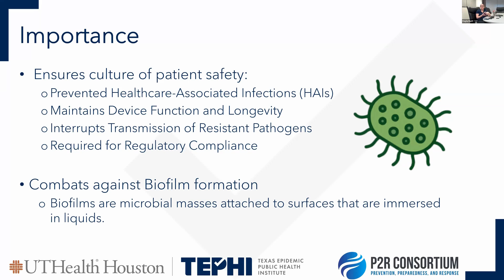As you've heard me mention before, the first primary thing with any device is determining what Spaulding classification it needs, whether it needs cleaning, high-level disinfection, or sterilization. That will always be listed in the manufacturer instructions for use, or the MIFU. That is the specific document of how that device should be handled, stored, cleaned, processed, pre-cleaning, cycle times of cleaning, when and how it should be used, everything. It will tell you in detail how to handle that piece of equipment.